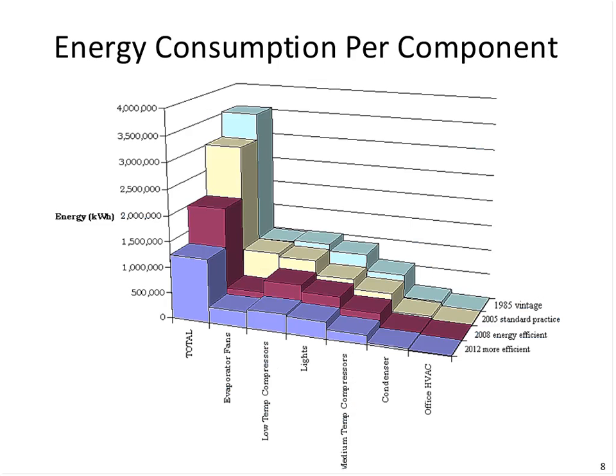So when assessing refrigerated warehouses, this is an example of where we've come. And notice in this graph here, we've got annual kilowatt hours along the left, and then along the bottom here, the total kilowatt hours and then those kilowatt hours attributed to evaporator fans, low temp compressors, the lighting, medium temp compressors, the evap condensers, and then a little bit of office equipment or air conditioning for office space at the warehouse. And then on the right, notice we've got 4 different types of facilities. These would all be the same size, but in 1985, the vintage type system we would see then and earlier than that, sort of a baseline for comparison reasons here.